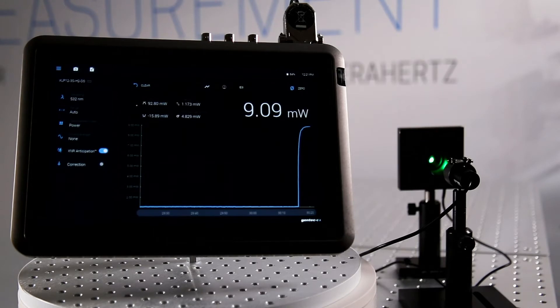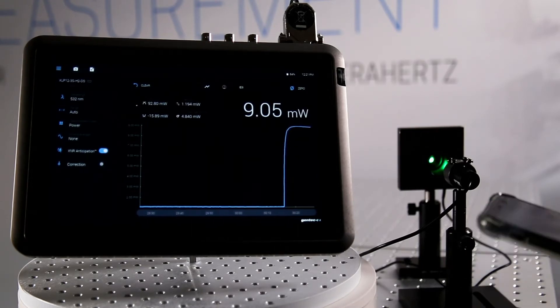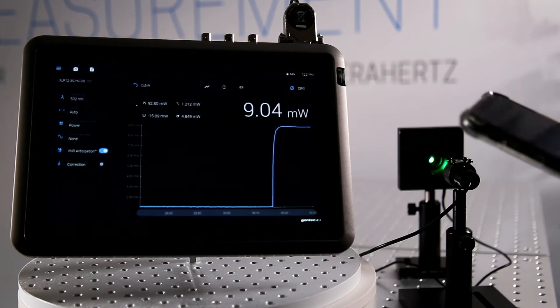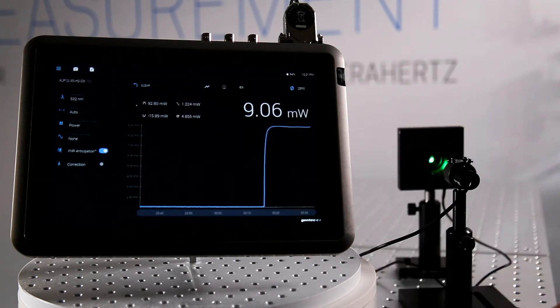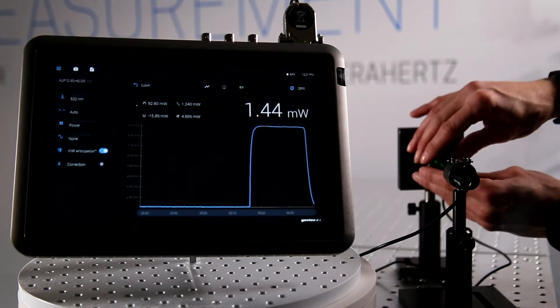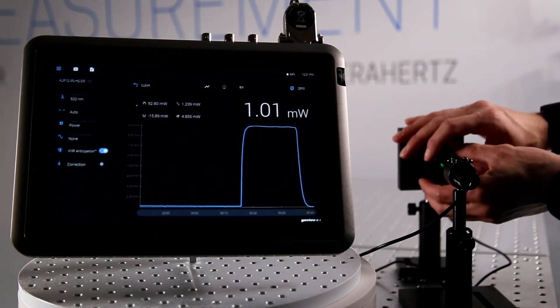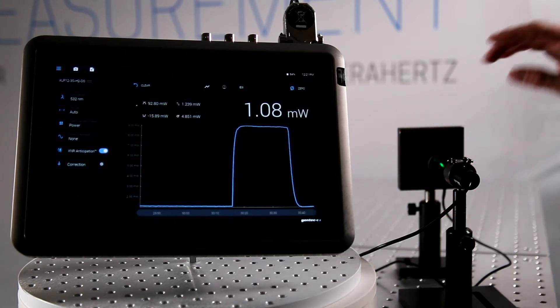It is 9.07 milliwatt. If I do the calculation — 9.07 divided by 1.1 milliwatt — I get a correction factor of 8.24, which I will apply to find the exact accurate power that I have out of this laser.